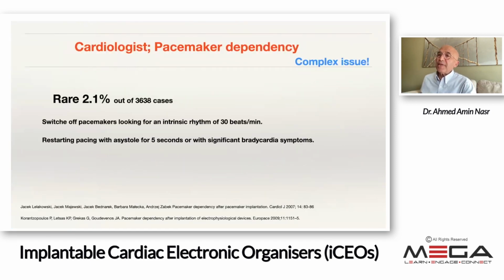The issue of pacemaker dependency is a tricky and complex one, even with no agreed upon definition. Thank God it is rare. In a study in 2007, they found only 2.1% out of 3,638 cases. They switched off the pacemaker looking for an intrinsic rhythm of 30 beats per minute. They restart the pacing if there is asystole for 5 seconds or significant bradycardia symptoms.